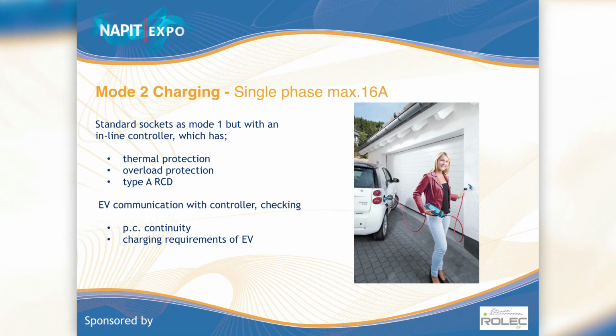Mode 2 is a standard socket, but they recommend an industrial type socket - a 60309/2 commando socket. With this socket arrangement, the pins are barrel-shaped and fit into a cylinder, giving total contact rather than a pin fitting into a U-clip, so the contact is better. The earthing pin on the CPC is also bigger, giving a better CPC connection.